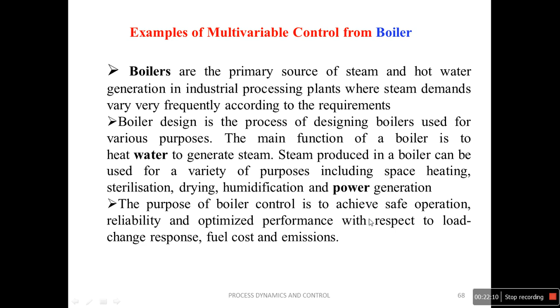Important controls in the boiler are drum level, fuel flow, air flow and flue gases. Already you know about flue gases. I think in the next semester we are going to discuss a subject called power plant instrumentation, where we will also discuss this. Generally the air flow is coming. What is the purpose of air here? In order to produce combustion, the fuel must be burned with a proper amount of air. The process of burning the fuel by combining with air is nothing but combustion. To get proper combustion, the air and fuel must maintain a desired ratio. The fuel to air ratio must be controlled.